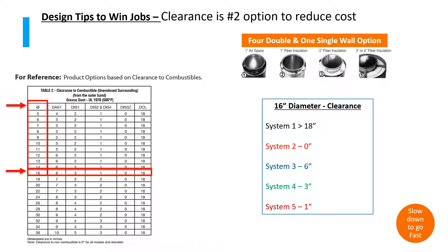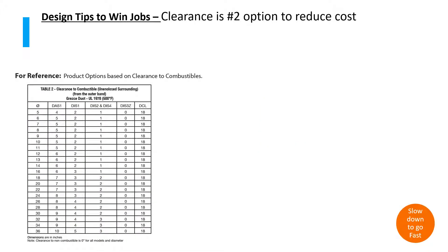In this practice exercise we're going to use a 16 inch diameter and determine the clearance from the outer wall of the duct to the combustible. The first system has a clearance to combustible of 18 inches, so that's going to be our DCL product. At zero clearance, System 2 is going to be the DIS 3Z product, and then your 6 inch, 3 inch, and 1 inch clearance options.